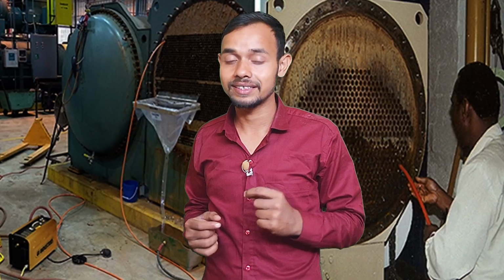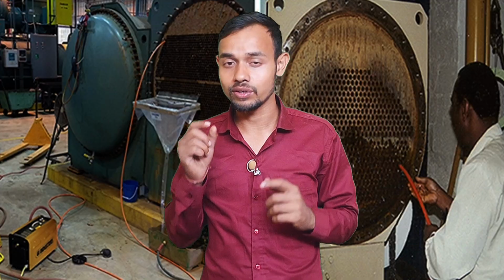Okay, friends, top reasons descaling is extremely important. First is heat transfer drop of 50 to 60%. Chiller tubes transfer heat from hot water to refrigerant. Okay, friend, and scale acts like insulation. Heat cannot move across it, so heat transfer is not possible. What is the result? Cooling fails and water is not cooled.